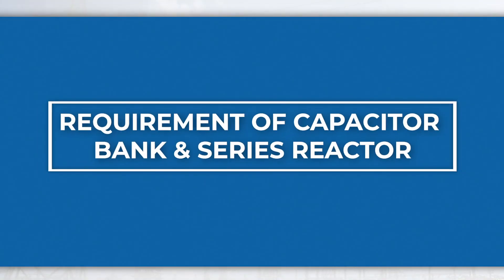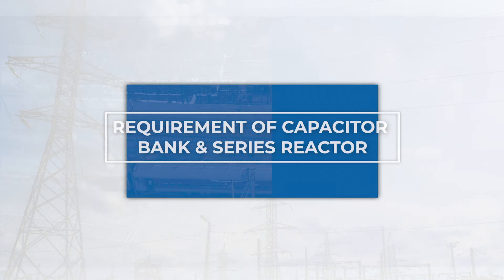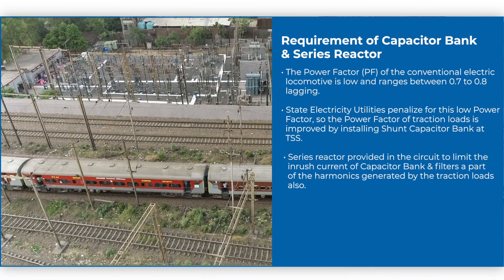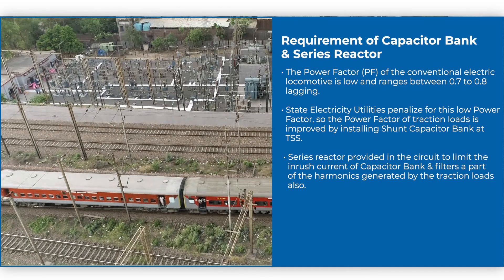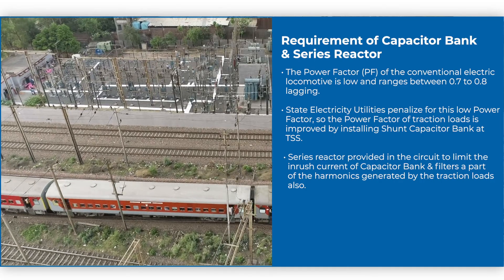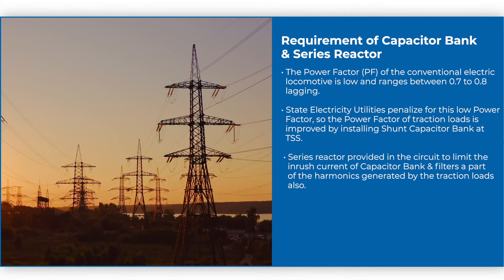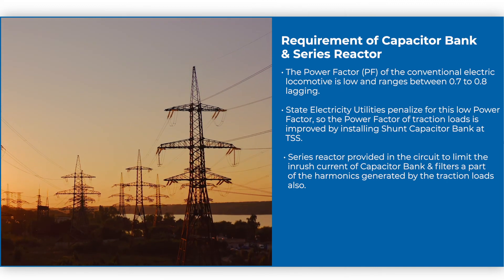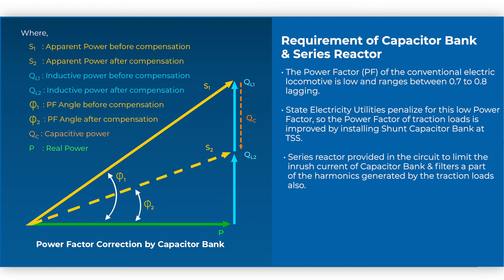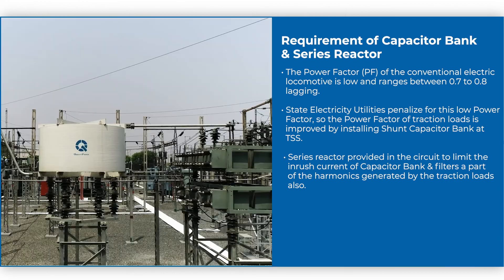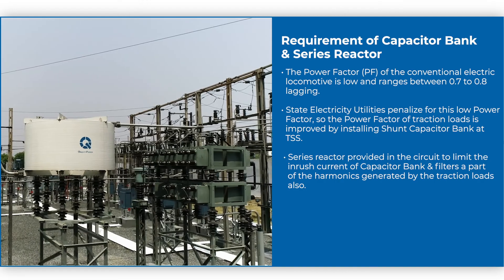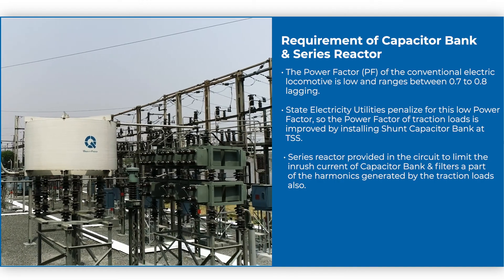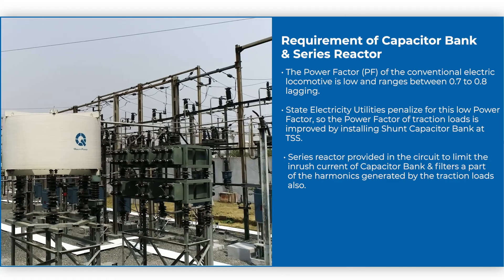The power factor of the conventional electric locomotive is low and ranges between 0.7 to 0.8 lagging. State electricity utilities penalize for this low power factor, so the power factor of traction loads is improved by installing a shunt capacitor bank at the TSS. A series reactor is provided in the circuit to limit the inrush current of the capacitor bank and to filter a part of the harmonics generated by the traction loads.